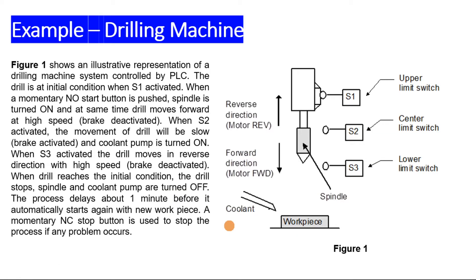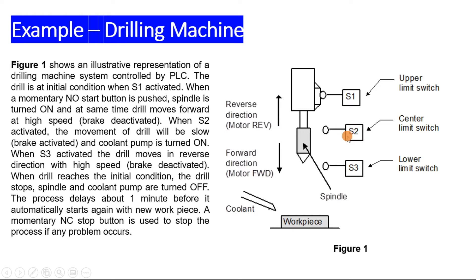We go to the example of a drilling machine using a step sequence, and we are going to transform it into a ladder logic diagram. Figure 1 shows an illustrative representation of a drilling machine controlled by the PLC. The drill at its initial condition is at S1. When a momentary normally-open start button is pushed, the spindle is turned on and at the same time the drill moves forward at high speed, meaning the brake is deactivated. When S2 is activated — meaning the drill has moved from S1 to S2 — the movement of the drill will be slow, meaning the brake is activated.